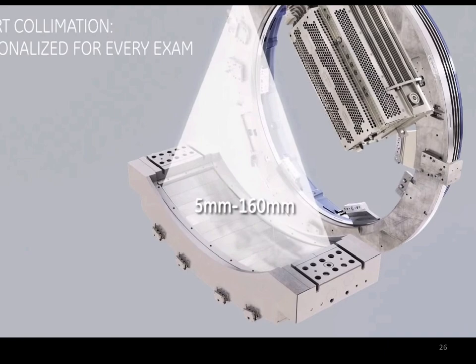So for doing the heart, usually it is not helical scanning. Usually we just put the scanner at one location that projects a shadow of the heart onto this detector and then take data in a rotation. The data you need for CT is essentially about half a rotation plus a little bit. So at 280 milliseconds per rotation, that means we need about 140 milliseconds to get the data we need for a full 3D volume. That's why it's fast, right?